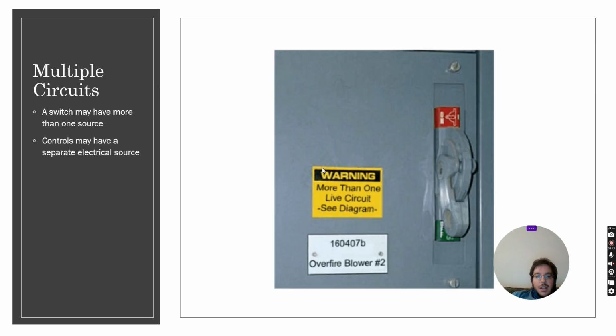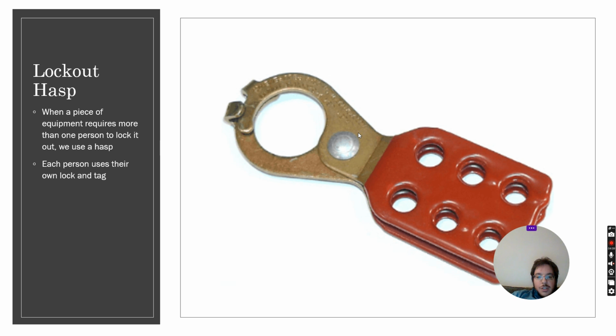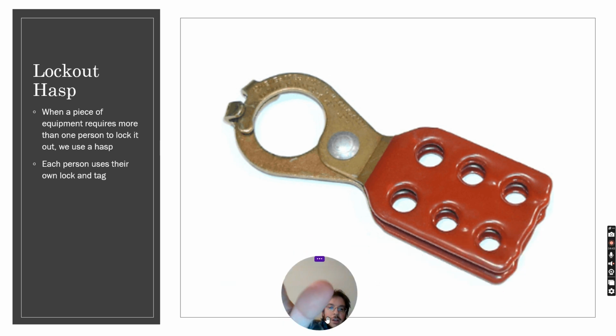Now, sometimes you will see a diagram that says more than one live circuit. This could be any kind of device or panel, and the reason is that in industrial equipment and some commercial equipment we can have 600 volts for motors, or 347 volts for lighting. We can have 208 volts for motors. We can have 120 volts for equipment or controls. We can have 24 volts for controls. 24 volts sometimes isn't dangerous, but still you want to be careful. So before you work on something, you want to check that you've disconnected all the different sources of voltage, and that you're electrically safe.